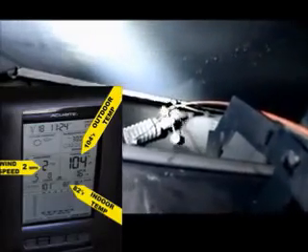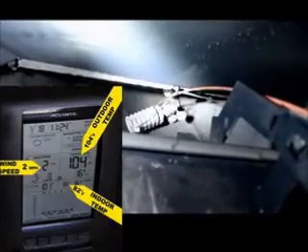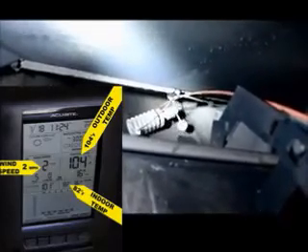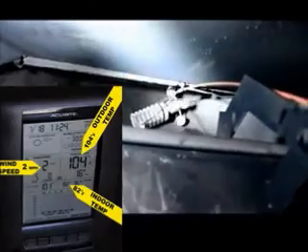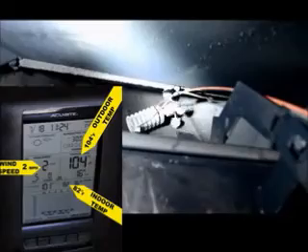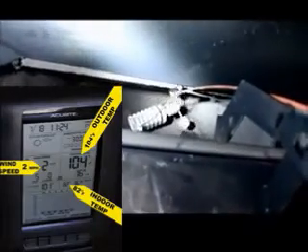Because the air-conditioning system is pressurizing the house and there is a wind blowing across the top of the chimney, cold air is pushed and pulled up the flue, turning the anemometer to indicate an upward flow of 2 miles an hour. Subsequent tests showed us that those rates were as high as 5 miles per hour.